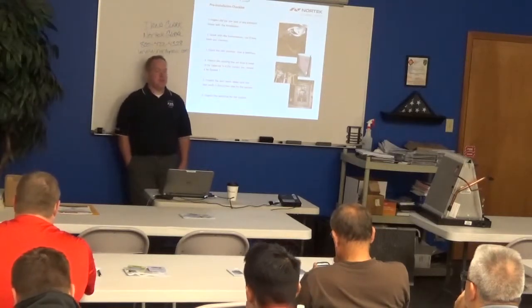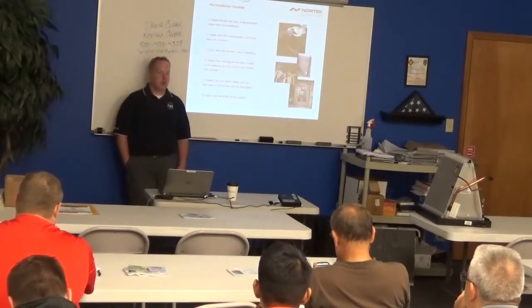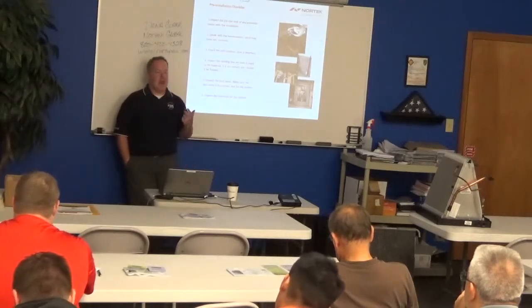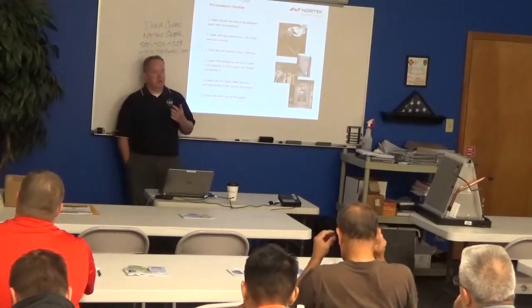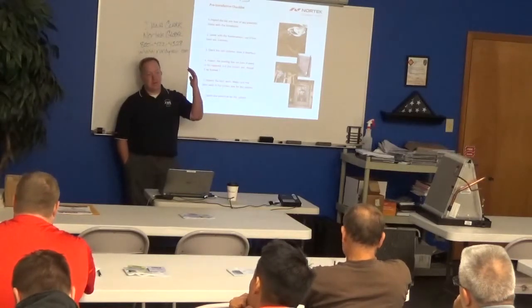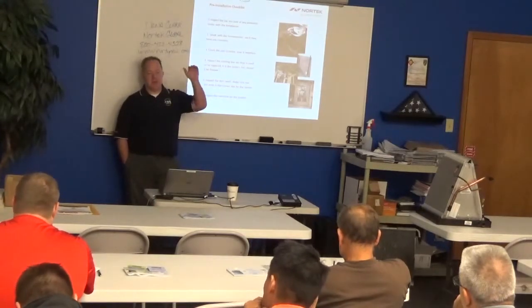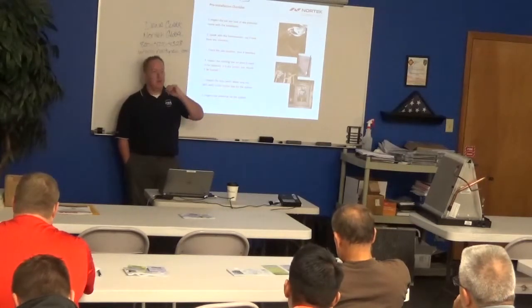We will be asked from time to time, let's say when a compressor dies, what do you think caused this compressor to die? And one of the first things I do is answer the question with a question. And that is typically, what does the layout of the piping on your line set look like? Are you pumping 25 feet up to an evaporator? And if so, if it's up in an attic, how does it enter into that attic? Is that line set just entering up into the attic and going straight over to that unit? Do we have an inverted vapor line trap?